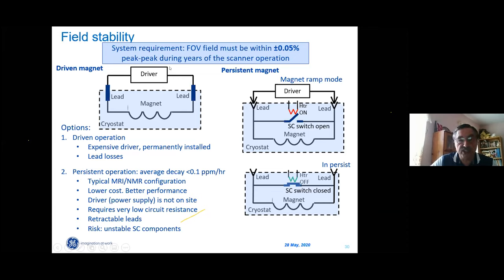So there are multiple techniques that are used to improve stability of the driver. One of them was used by the Iseult magnet. All commercial, standard commercial magnets operate in so-called persistent mode. So we ramp the magnet and then we disconnect, completely remove current leads, and the magnet is in persistent mode. In order to do this, we need to use a superconducting switch here, which is open. It's a thermal switch, which is open when we ramp the magnet and which is closed when the magnet is in operation.